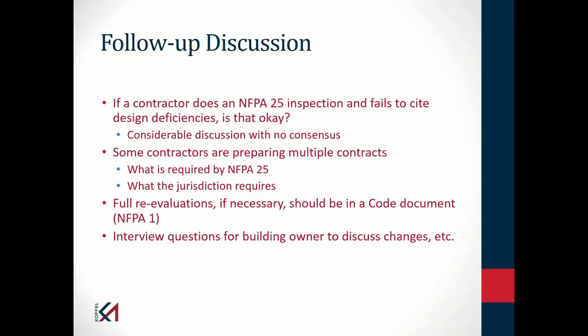So do we need to have some type of reevaluation of a system at a period of time? Some of the codes that talked about this, there's no specific requirement that says every 5 years, 10 years, somebody needs to go in and reevaluate the design and installation of the system. Right now, we kind of leave it up to the owner to manage change, identify when changes are made, and how they might have an impact on the system. You may not know the requirements well enough, but call somebody in, a contractor, consultant, engineer, maybe even the fire marshal, for a specific focused visit and say, is my system going to be adequate if we make this change?